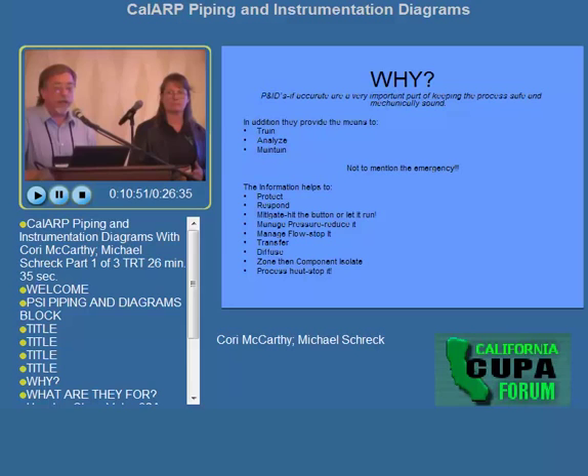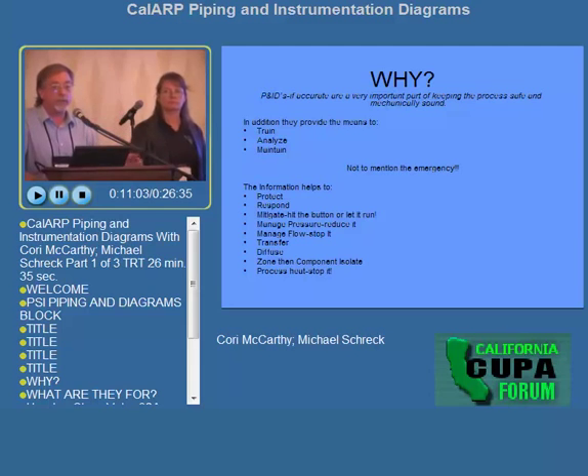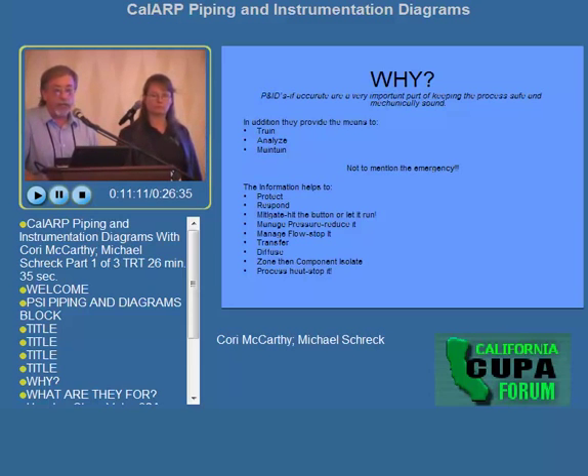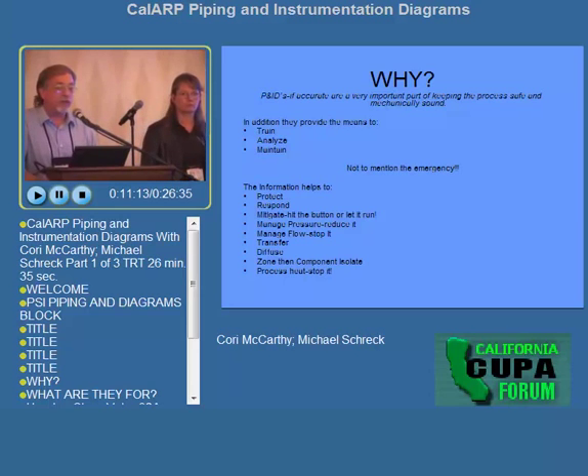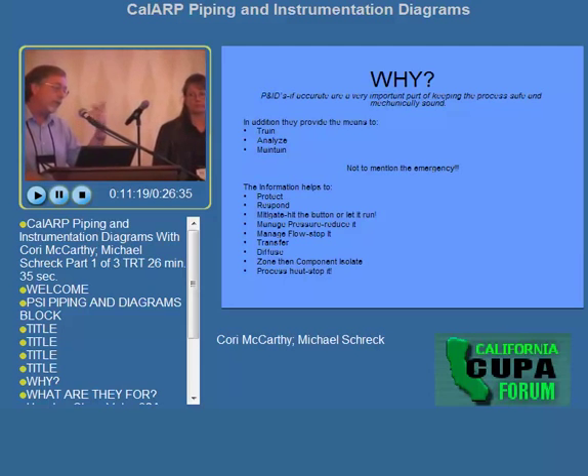What happened there was a mechanic isolated a heat exchanger improperly without turning the proper valves and trapped liquid refrigerant between two valves and a heat exchanger. If you heat up that liquid refrigerant, it expands up to a thousand times. There's nowhere to store that vapor, so the heat exchanger exploded, and a woman was buried for seven hours under the rubble before they found her. No head count sheets, no P&IDs — the Chemical Safety Board is investigating that incident.